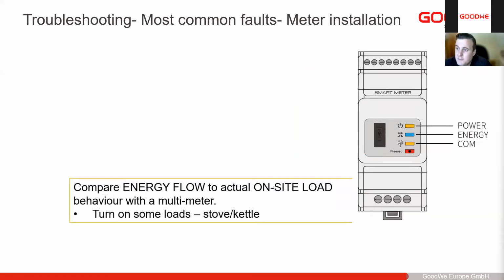So when we install our smart meter, the smart meter can give us a lot of information. On PV Master, it makes life easy for us. We can just open it up and see which direction the power is flowing. But very often these are installed even with grid ties just to power limit that grid tie on its own. There we don't have any display or any meter data on any apps. We only have the smart meter to look at, but this is a good way to quickly see exactly what's going on.